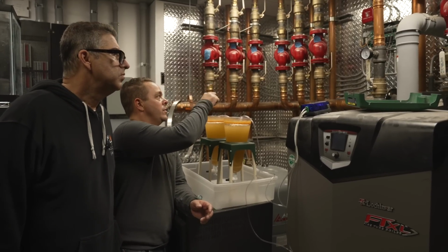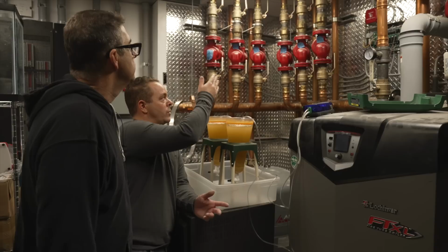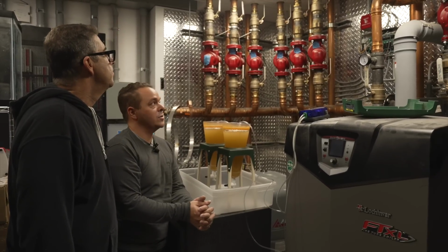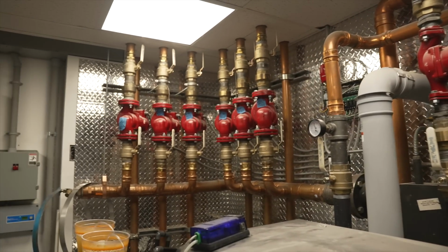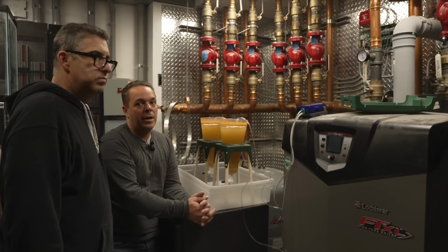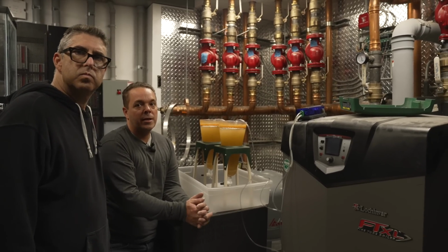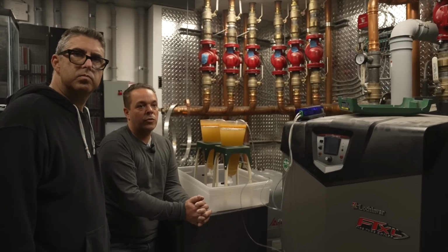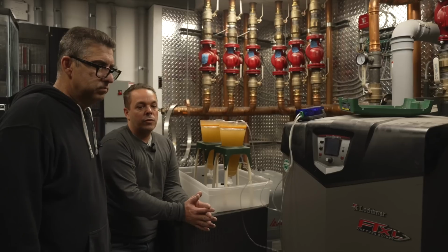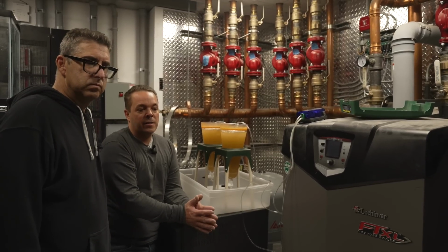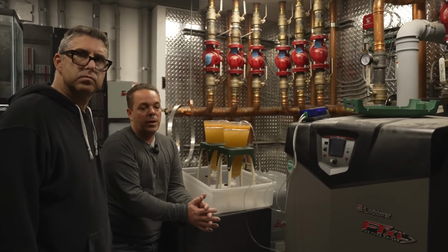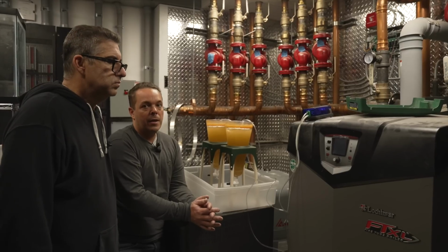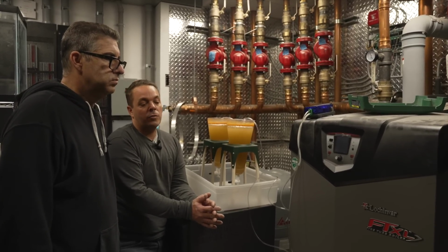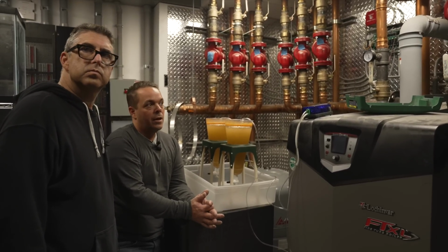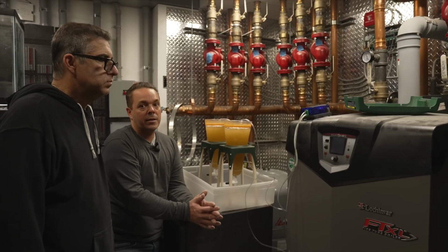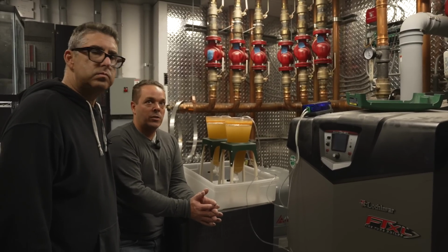Each heating zone has its own circulator, which are these red pumps here that supply water to titanium heat exchangers. The copper pipe transitions to a polyethylene pipe. So we chose to go with polyethylene pipe once it left this room so that the corrosive saltwater air wouldn't oxidize or eat through the copper pipe. The polyethylene pipe is not affected by that. The polyethylene pipe connects right to the titanium heat exchanger, and also returns the water back in polyethylene, and we convert it back to copper once we enter this room.